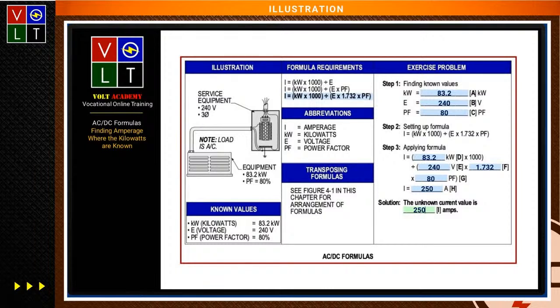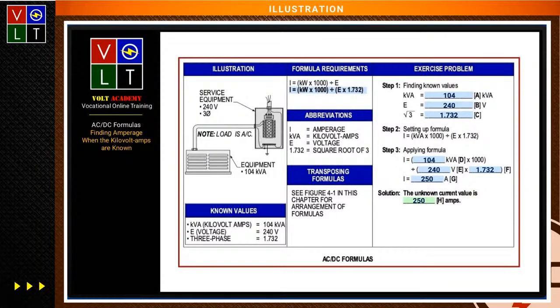Now, the next one you're going to look at is where the kilovolt amps are known. Okay. So we're showing you the same type of setup. The equipment here is 104 kVA. It's 240. Once again, I'll take the kVA times 1,000 to put it in VA form. And then I will take the voltage, 240 volts times 1.732, 416, and divide that into the 104,000. That's going to give you 250 amps. So you can see we did the same calculation. Instead of kilowatts, we did kVA, and I still came up with 250 amps.